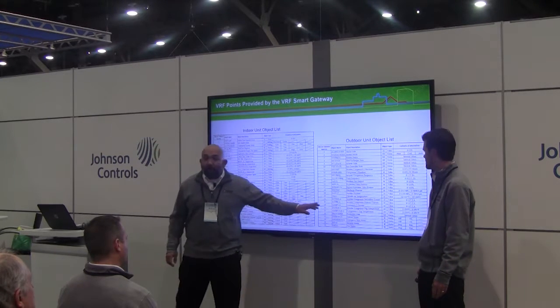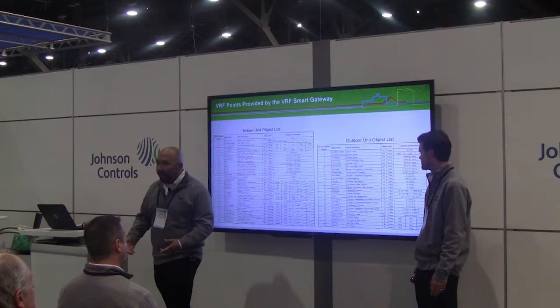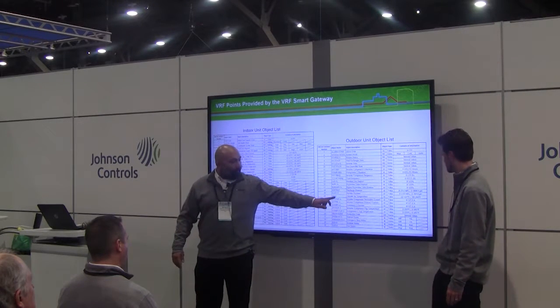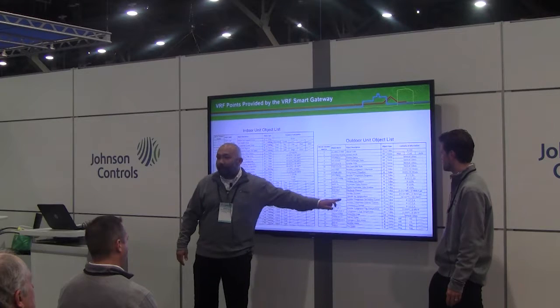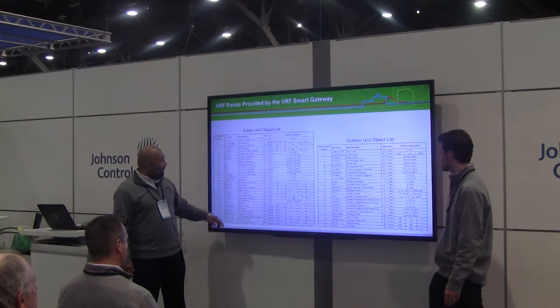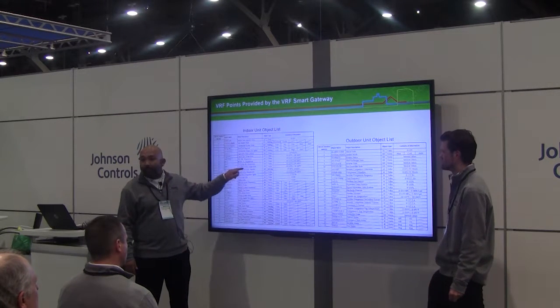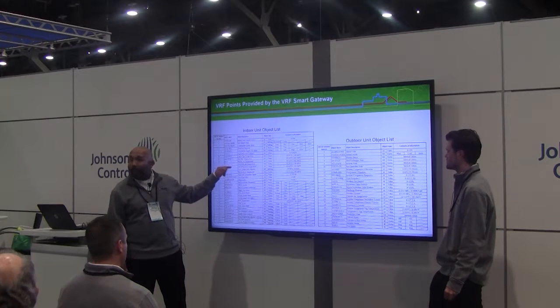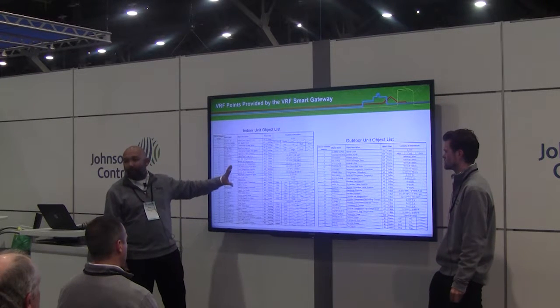So, to the point I made earlier about having to add sensors with current front ends—no more adding an ambient temperature sensor, there it is. No more adding a zone temperature sensor, because there it is. We even give you the differential of the air going in and out of that indoor unit, already calculated for you.